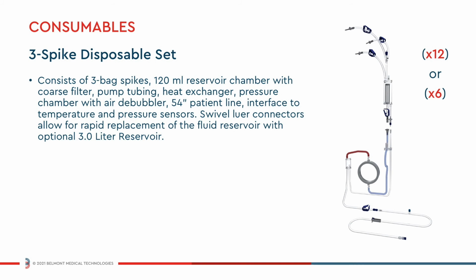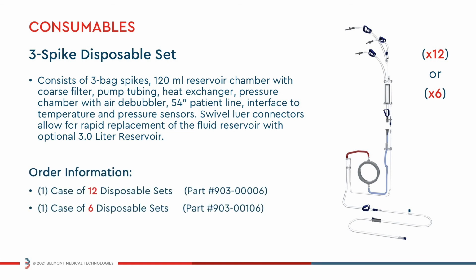The Belmont 3-spike disposable set contains everything you need for a procedure and is the only consumable required to operate the rapid infuser at its full range of flow rates. The disposable set consists of 3 bag spikes, a heat exchanger, a 54-inch patient line, and a 120 milliliter coarse blood filter reservoir. Quick connections below the reservoir allow for easy and rapid replacement with the optional 3-liter reservoir. The 3-spike disposable can now be ordered in 2 convenient quantities of either 12 or 6 disposables per case.